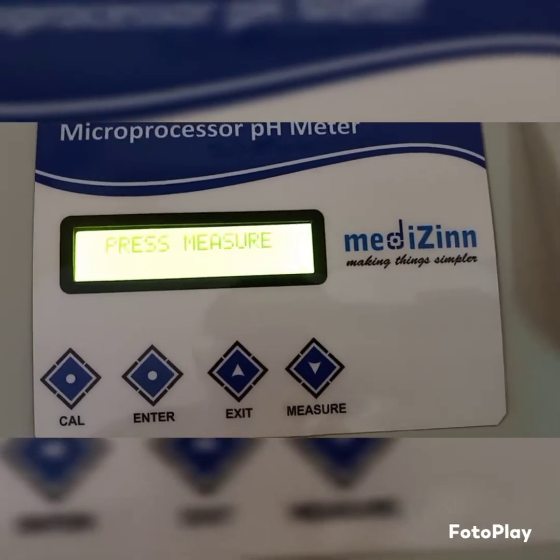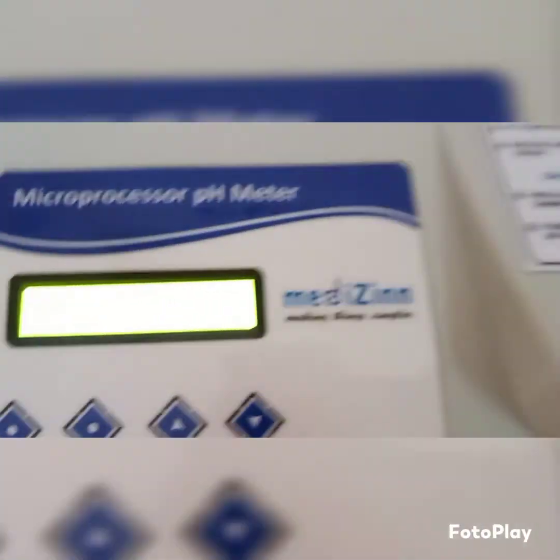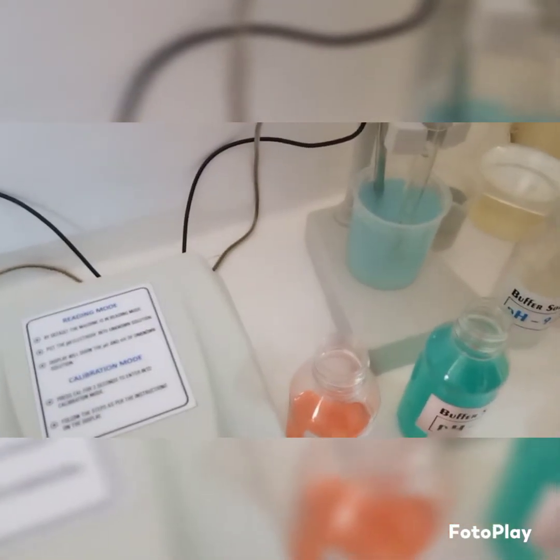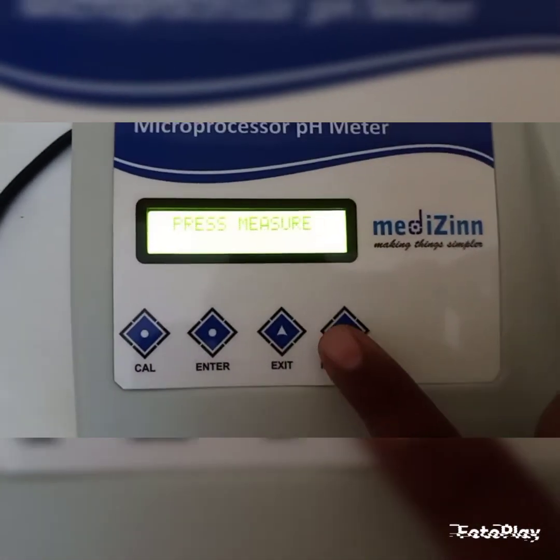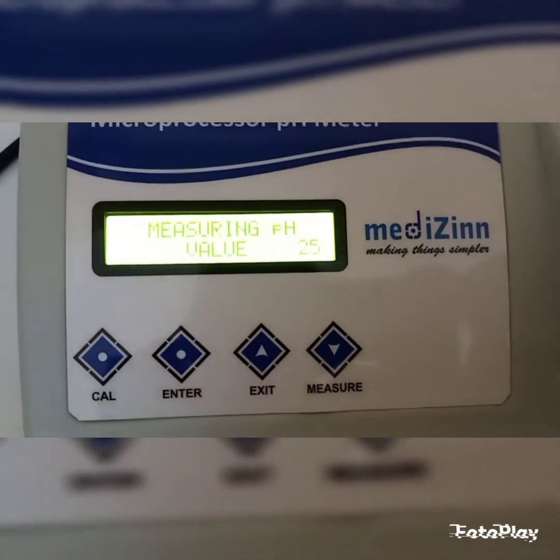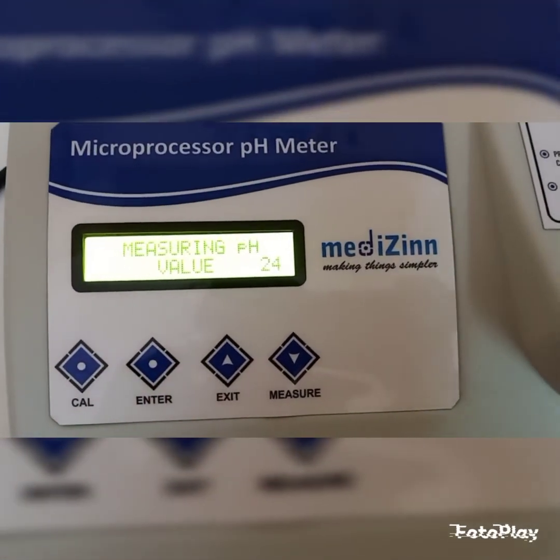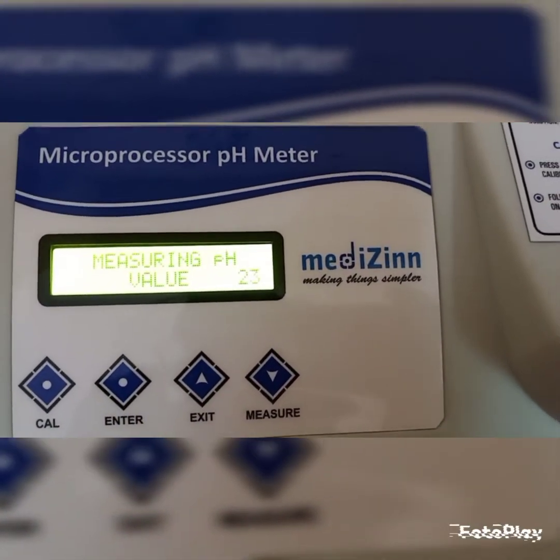For the measurement mode, press measure after putting the pH electrode and temperature probe into unknown solution. For the video purpose, we are using 9.2 pH buffer. So put electrode and temperature probe into 9.2 pH buffer and press measure. A countdown timer start.